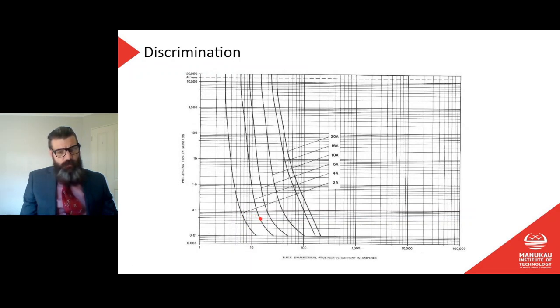Now, if this line here started to overlap any of these ones, let's say it took a sharp turn to the right and went down here, then that means if we had one of these larger devices protecting this smaller 2 amp one, then at this point here, the 2 amp circuit breaker would fail to trip and the 4 amp circuit breaker would trip instead. That's if my 2 amp line started going this way, which is not right. We always want the 2 amp one to trip first.